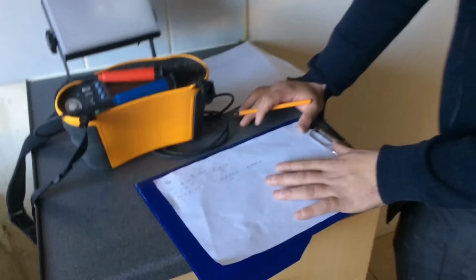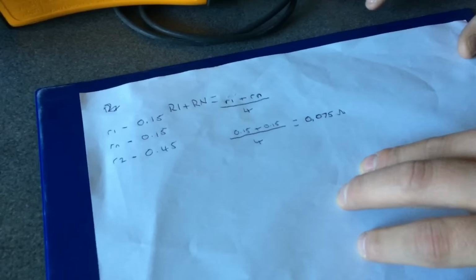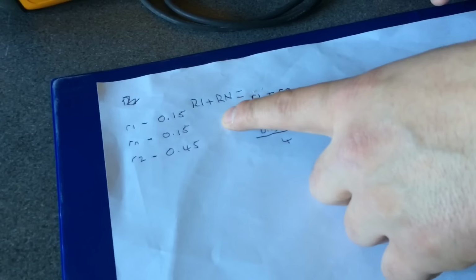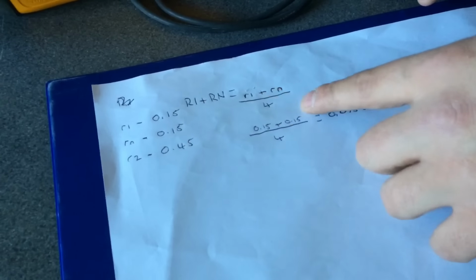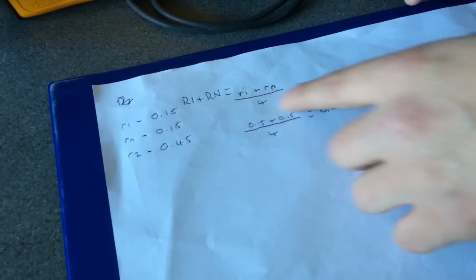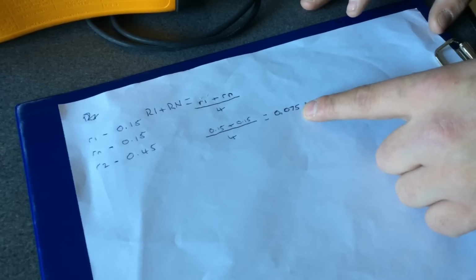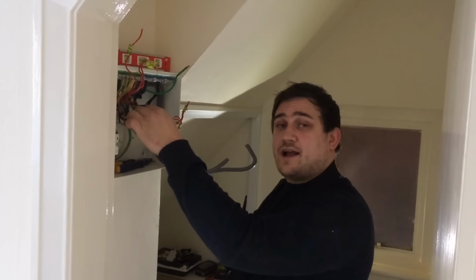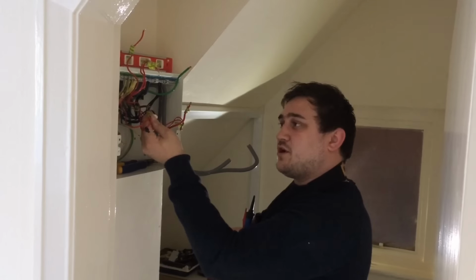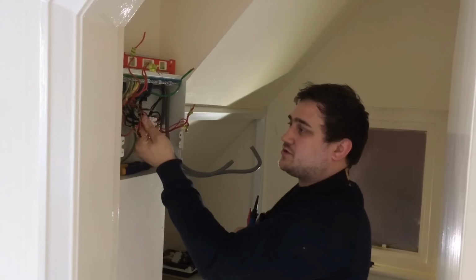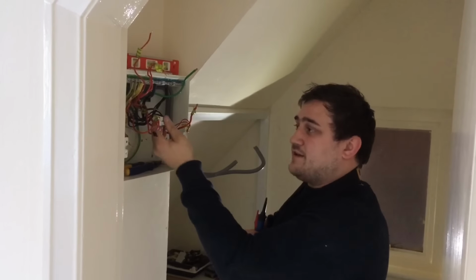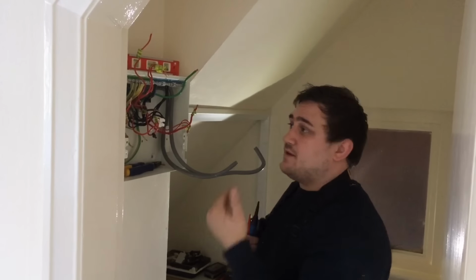So now I've done my end-to-end tests. I'm now doing my figure of 8 tests. And I've calculated my big R1 and big Rn by little r1 plus little rn divided by 4. That will give me a reading of 0.075. I'm allowed a plus and minus of 0.05 either way of that reading at each socket outlet and at the distribution board. Now we've got our calculated reading. In the board I've linked the opposite line to the opposite neutral in connector blocks. That's for our figure of 8. I identified the opposite legs when I removed the old consumer unit and put the new one on.